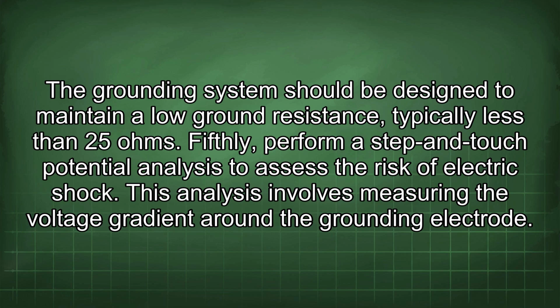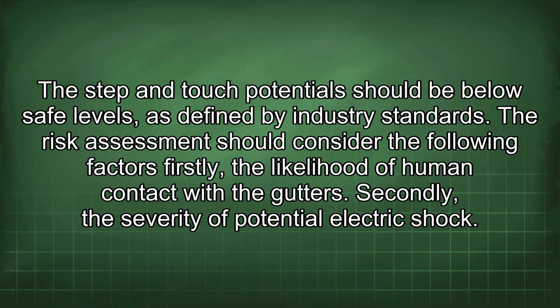Fifthly, perform a step and touch potential analysis to assess the risk of electric shock. This analysis involves measuring the voltage gradient around the grounding electrode. The step and touch potential should be below safe levels, as defined by industry standards.